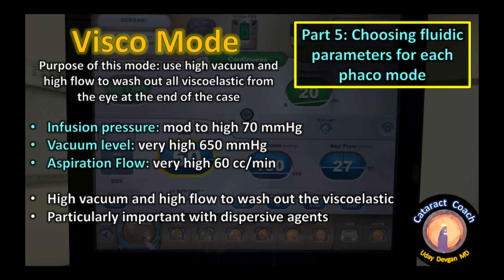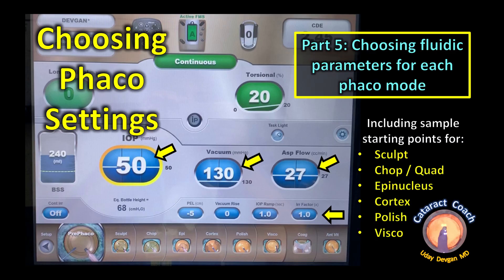Capsule polish mode uses low vacuum to remove small bits of lens material adhered to the posterior capsule: low infusion pressure, low vacuum, low flow — careful not to damage the posterior capsule, just aspirating off small adherent bits. Finally, viscoelastic removal mode uses high vacuum and high flow to wash out all viscoelastic: high infusion pressure, very high vacuum, very high flow — especially important for removing dispersive agents. I hope you've enjoyed this series; there will be more to come. Thank you for watching.